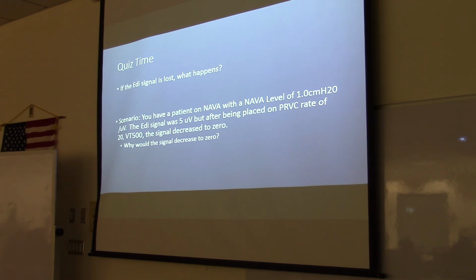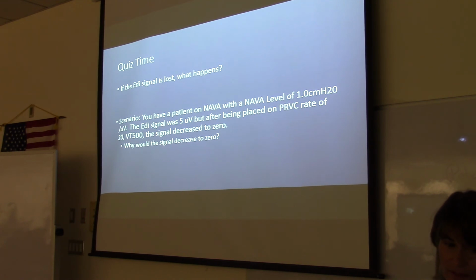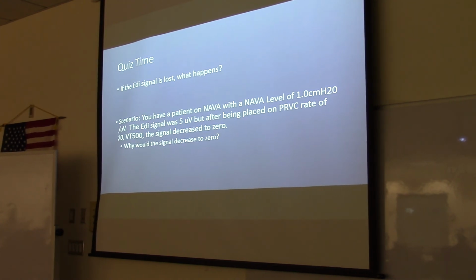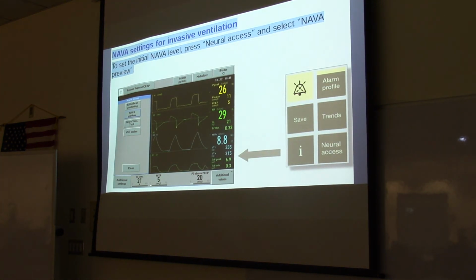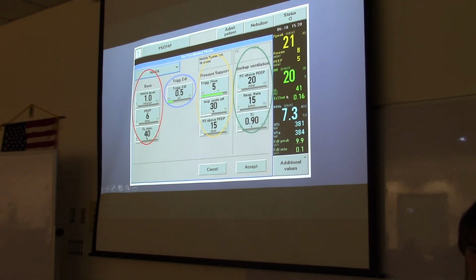If the EDI signal is lost, what happens? There's a backup ventilation that'll kick in. Yes. So we've got flow-by sensitivity that'll initiate a breath. And we've got backup pressure support set. So it goes into just pressure support ventilation. Or if there's apnea, then it'll start ventilating the patient. There should be an apnea setting, right? Yeah, you want to go back to it real quick? See if I can find it. Yeah, so there's backup ventilation if there's apnea, and then there's backup pressure support if the signal is lost. Oh, so there's both. You're covered in many ways. Yes.